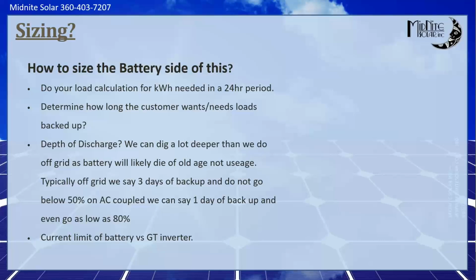And in that same mentality, if you're sizing that battery and building that battery for a battery backup system for just utility outages, we can be a lot more aggressive with that battery. Like, the old analogy of if I've got a lead acid battery, never drain it below 50% ever, ever, ever. Well, if you're using an AGM type battery and it's a battery backup system for the utility grid, you can be a lot meaner to that battery because the outages are fewer and far between.